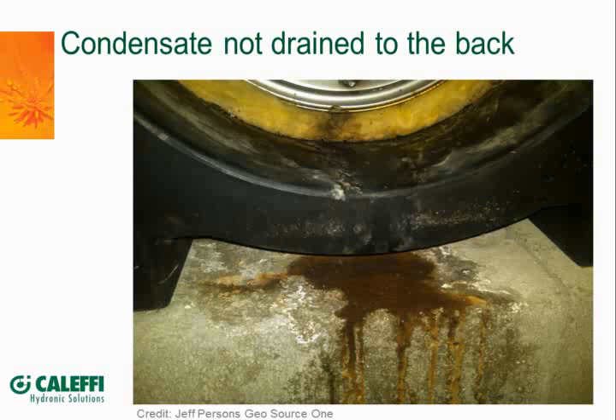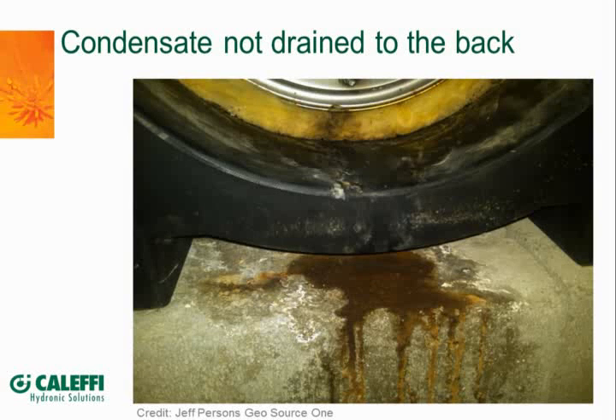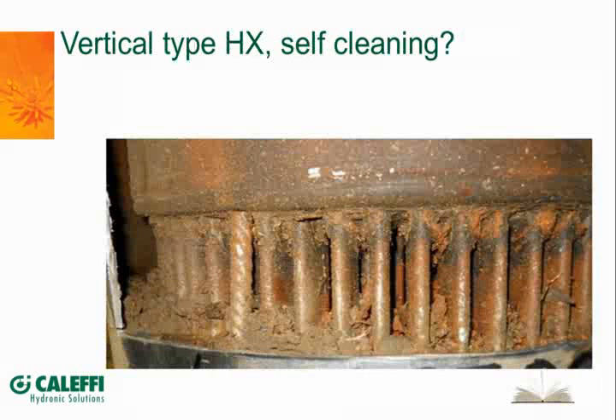Yes, this is a situation where the boiler body was not level within the frame, and it was causing condensate to pool towards the front side of the boiler. That condensate becomes very acidic, and not flushing itself completely through the condensate drain at the back of the boiler was likely the explanation for perforations at the weld seam around the front side of the boiler. It's even eating away the concrete block underneath. That's right. And there's about a quarter-inch divot in that concrete block where the condensate was dripping out onto the block. So real low pH in that condensate water. Oh, yes.